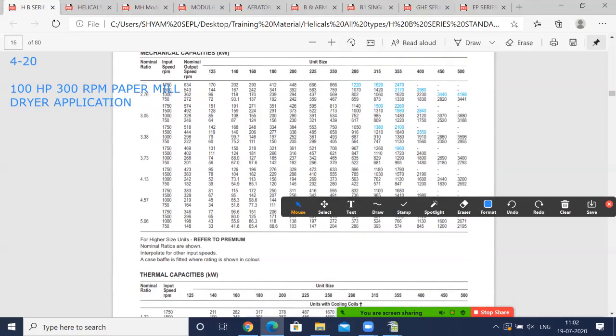at 1500 rpm you can see 296 rpm, so you get the 300 rpm mark, and you get the first capacity as 65 kilowatt. Now 100 hp is 75 kilowatt. For a paper mill application we normally select a safety factor of 2 because the load is high. So 75 into 2, that is 150 kilowatt. What's the nearest? Here, as you can see, 171 and 125. So you can give both of these options. Models will be 180 and 160.